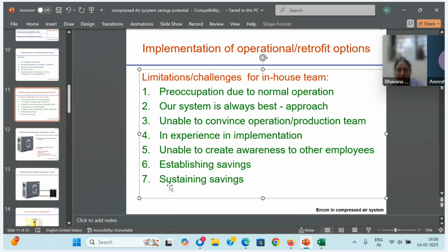See, typically for higher capacity, more than 55 kilowatt, the motor efficiency is more than 94-95%. So we may save only just 5%. The benefit of BLDC or permanent magnet motor, whatever I studied, Ingersoll Rand has been giving this permanent magnet motor. They were not able to establish the savings actually, whereas we can achieve much more than this 3 or 5% by reducing pressure or optimizing other things.